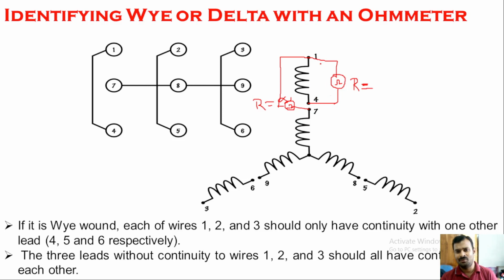So if you have resistance only between these two terminals, you can almost ensure that it is the star connection. But don't jump to the conclusion. We have to check the other terminals as well. So let us take the next terminal. Let me assume I have taken terminal 3 and I measure the resistance with respect to the next terminal. For example, I have connected between these two, and a small resistance value will be present here. Since I have already got a value for 1 and 4, I am not going to use those two terminals. The remaining terminals I am going to check with respect to 3: 3 and 6, 3 and 7, 3 and 8, 3 and 5, 3 and 2. All of these are going to give me infinite resistance except 3 and 6.